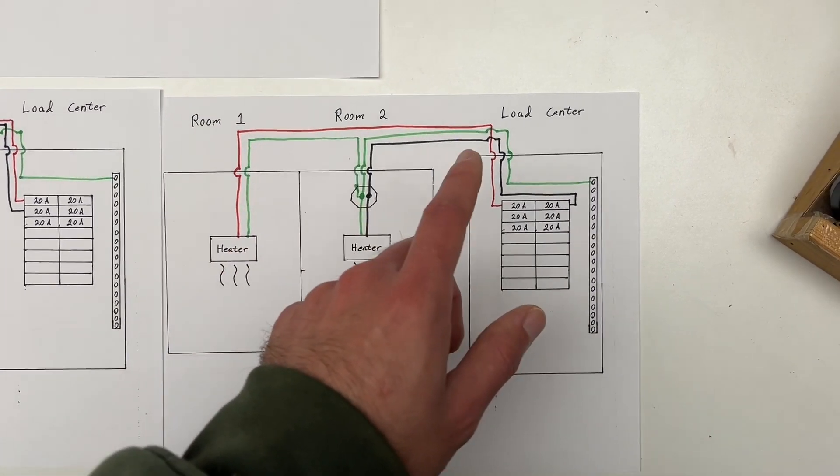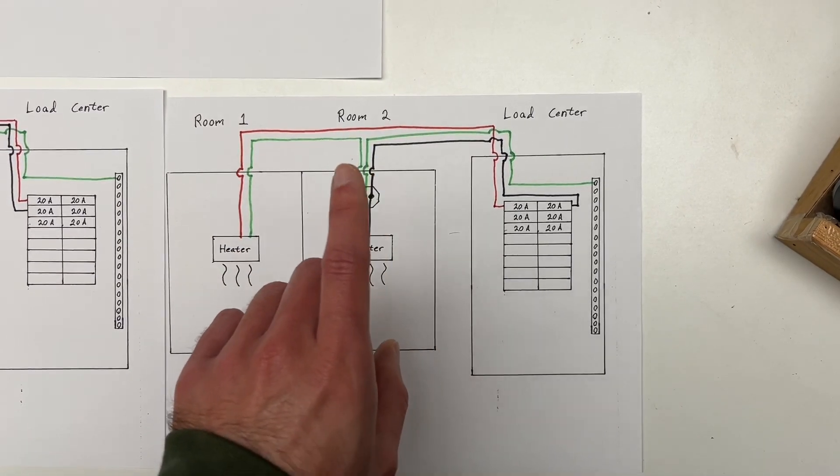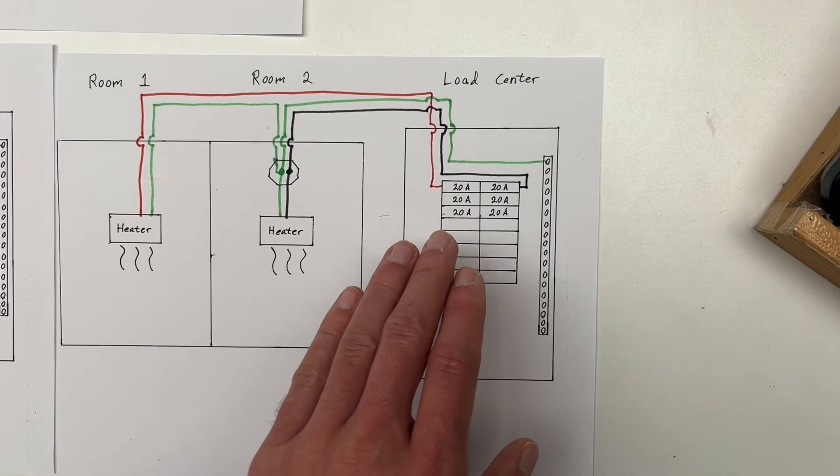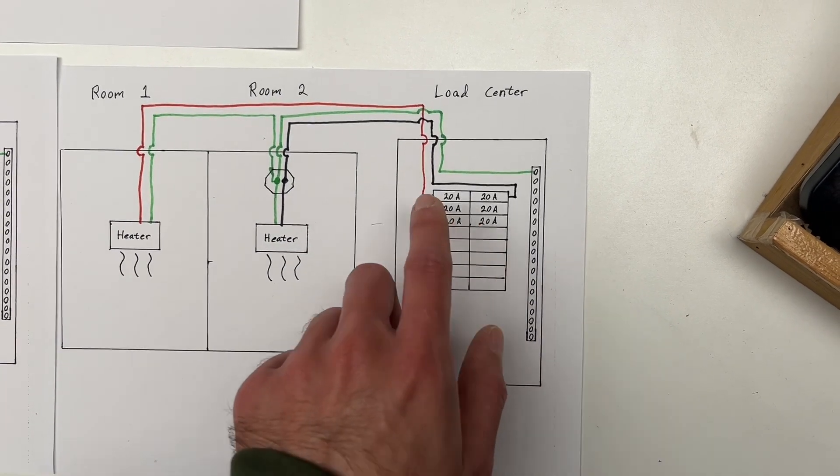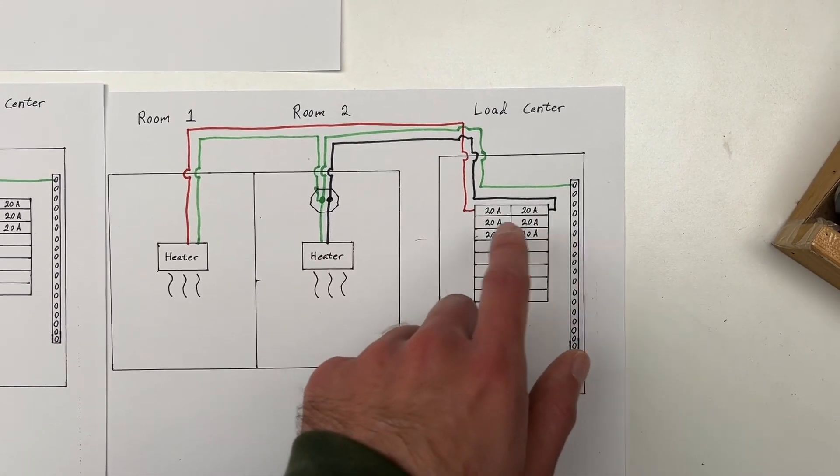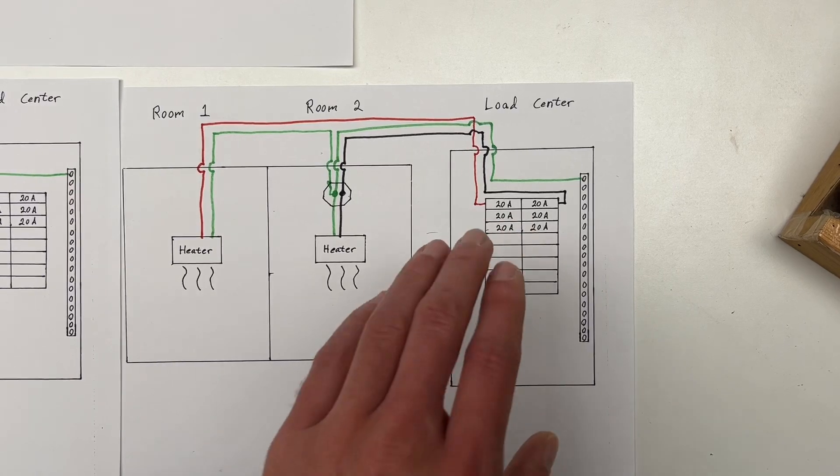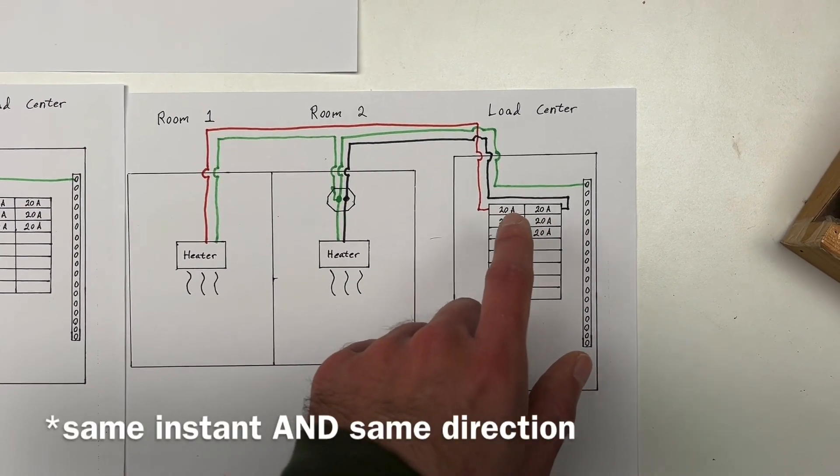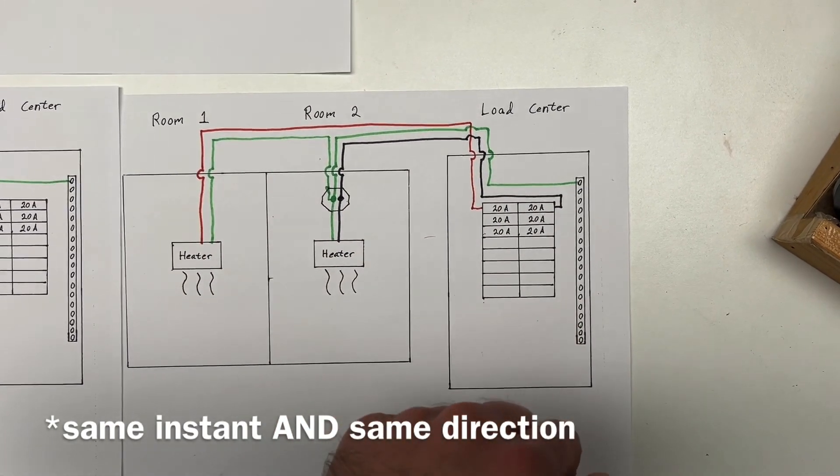So, aren't you going to undoubtedly overload the neutral wire? Well, not if you wire the breakers correctly. So, in this configuration, as shown, you actually could overload the neutral wire, because these horizontally adjacent breakers are what we call on the same phase. So, in other words, they are going to flow electricity at the same instant, and that means that 20 amps plus 20 amps would equal up to 40 amps back on the neutral wire.